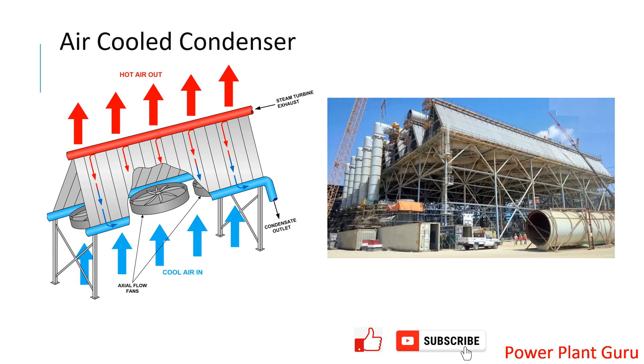As the name suggests, an air cooled condenser is used in places where you don't have much water availability. To make it effective, the air should be of lower temperature. In Indian climatic conditions you may find air cooled condensers in places like Rajasthan, where there is relatively higher temperature but scarcity of water. You will also find them in Canada or Europe, where there are environmental pressures to reduce water consumption or where water is not available and the air is pretty cold.